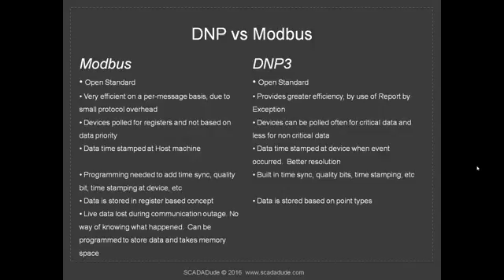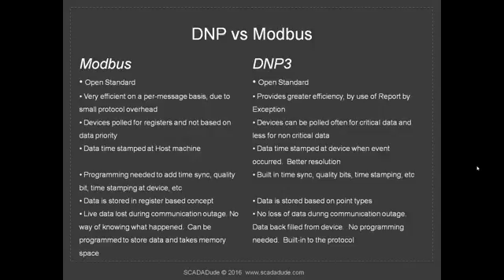The biggest problem with Modbus is sometimes when I'm talking to my device I lose communication. During the time that I lost communication I have no idea what the values are — that can be an issue. We can write a program and store it, but again that takes memory. DNP3 on the other hand has it in the protocol; it's all there, you don't have to do any programming.